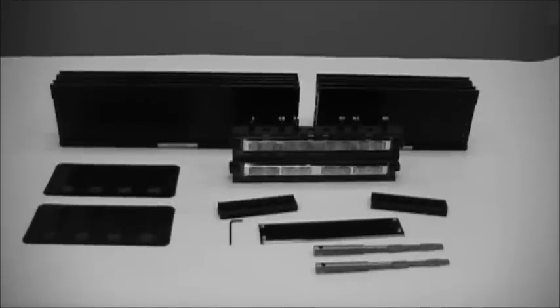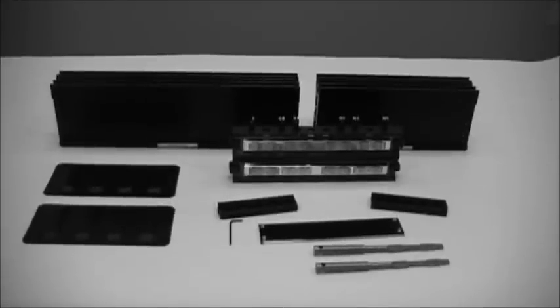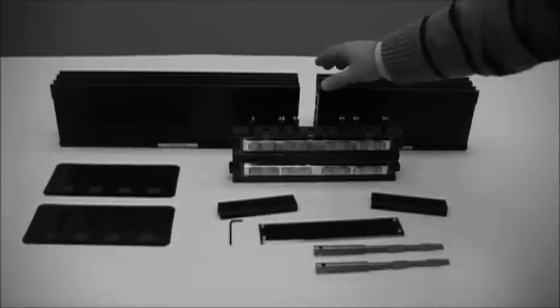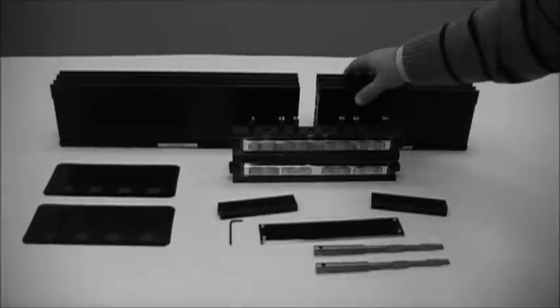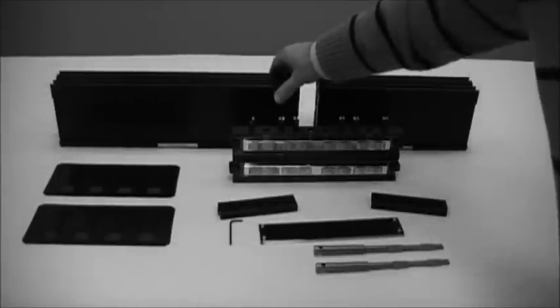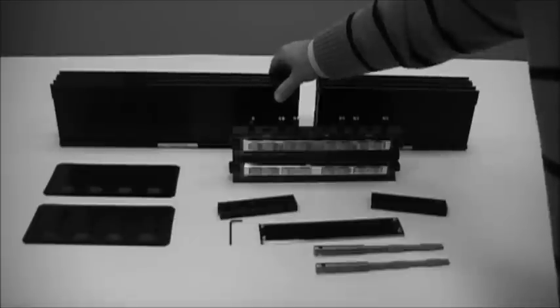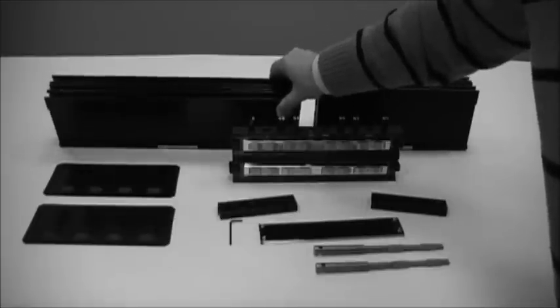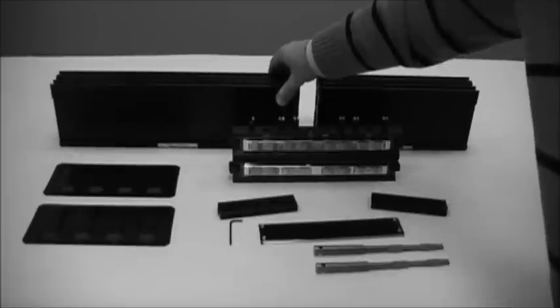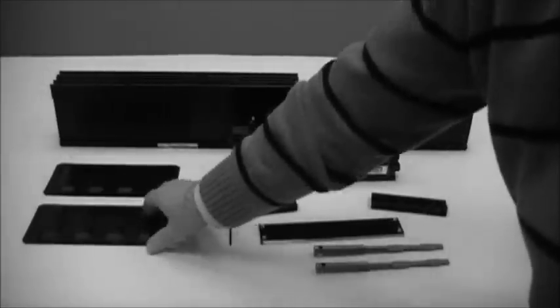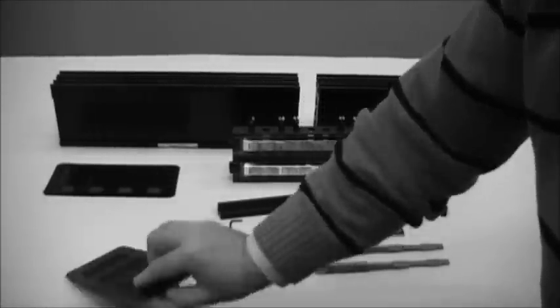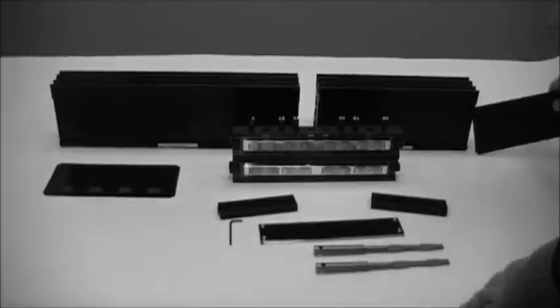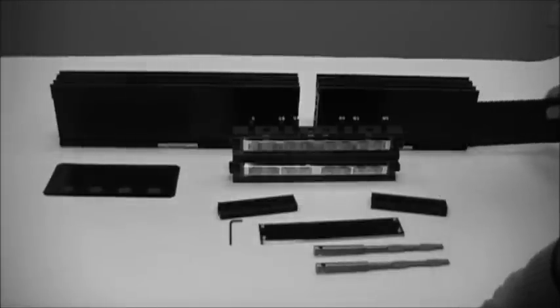The first step is to get all the hardware installed on the bus because as you start to install the joiner kit, the bus will flex. It's flexible and will push out and be difficult to install those pieces after the fact. So we'll go ahead and start to put those in so that we can be ready to install the joiner kit.